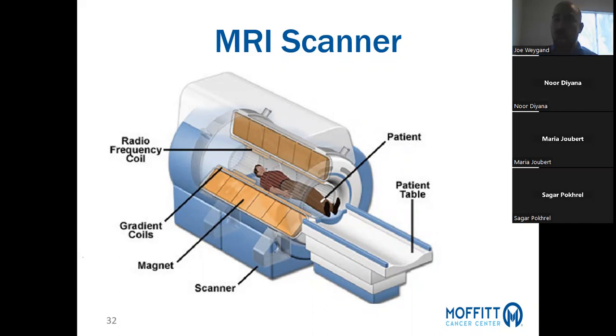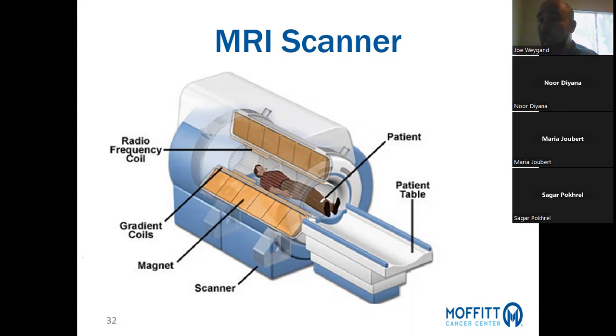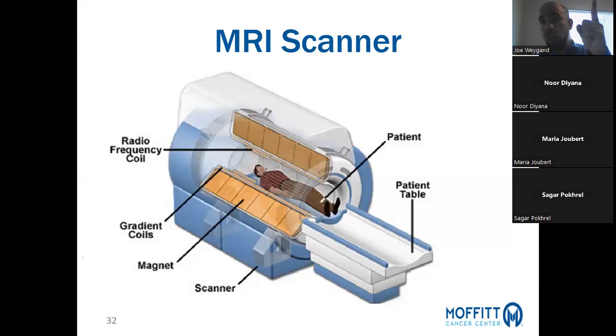We can now understand all the components of an MRI scanner. You have the table that moves in and out where the patient lays. You have the external magnetic field — the B0 field — which polarizes the spins and creates the magnetization. You have the gradient coils, used for spatial encoding to help produce an image. And you have the radio frequency coils, which serve two purposes: they generate the oscillating magnetic field B1, which flips the magnetization from the longitudinal axis into the transverse plane; and when in receive mode, they detect the signal coming out of the patient that we ultimately use to make an image.